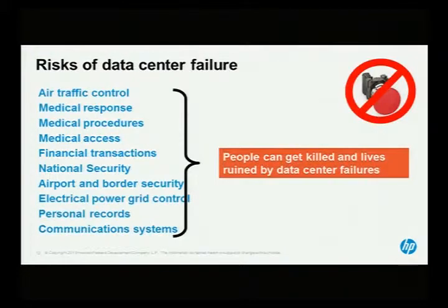Where do these risks come from? Air traffic control. Can you imagine having a data center where you have the air traffic controllers tied in and somebody hits an EPO switch? Talk about delays on the ground. Never mind the poor guys upstairs. This is actually what initiated our ability to get some changes into the code, because a lot of the authorities having jurisdiction are fire marshals, and they're directly tied into 911 call centers.